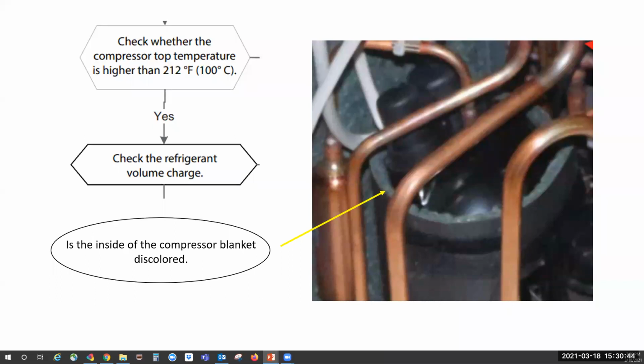Restriction in airflow of the evaporator on heat pumps can cause the compressor temperatures to run high. So you're looking for a plugged coil, possibly dirty filters, and once again, burnt wires. Also, if you want to see if your compressor's running hot, which we will have you do especially if we get a P6 code, pull that compressor blanket off and look to see if it's discolored or looks like it's been hot. Maybe look at the stickers to see if they're melted. Any indication that something's been hot in there, it's a good idea to just go ahead and replace the compressor. Sometimes you might get lucky and be able to ohm this out and see if the compressor's bad, but usually it's more of a visual check.